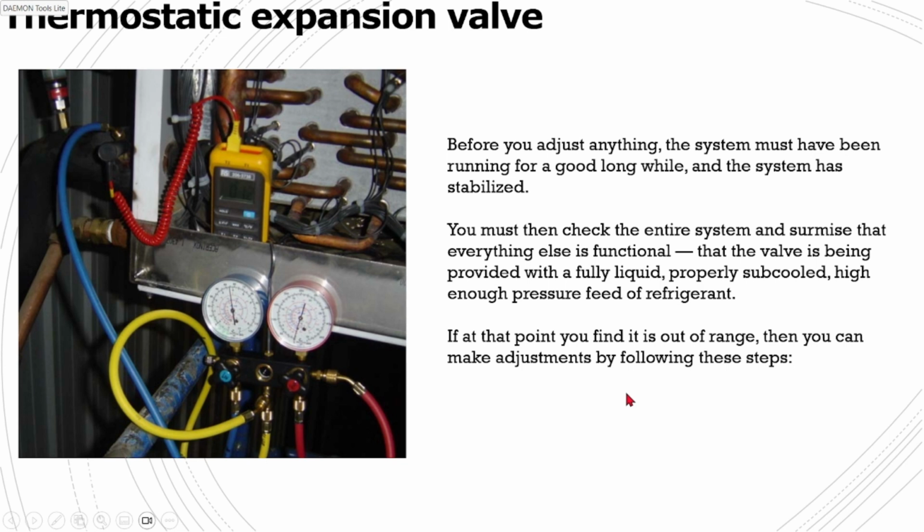Normally expansion valves are factory set devices. You don't want to touch them, but once you replace one, if you find that system performance is not at a satisfactory level, then of course you have to adjust it. So how are you going to adjust? Before touching the system, you have to make sure that your system is charged at the correct level, with no air in the system, and all the system components are working fine. The refrigerant is subcooled to the necessary value, and the system has been running for some time at a moderate or normal load.